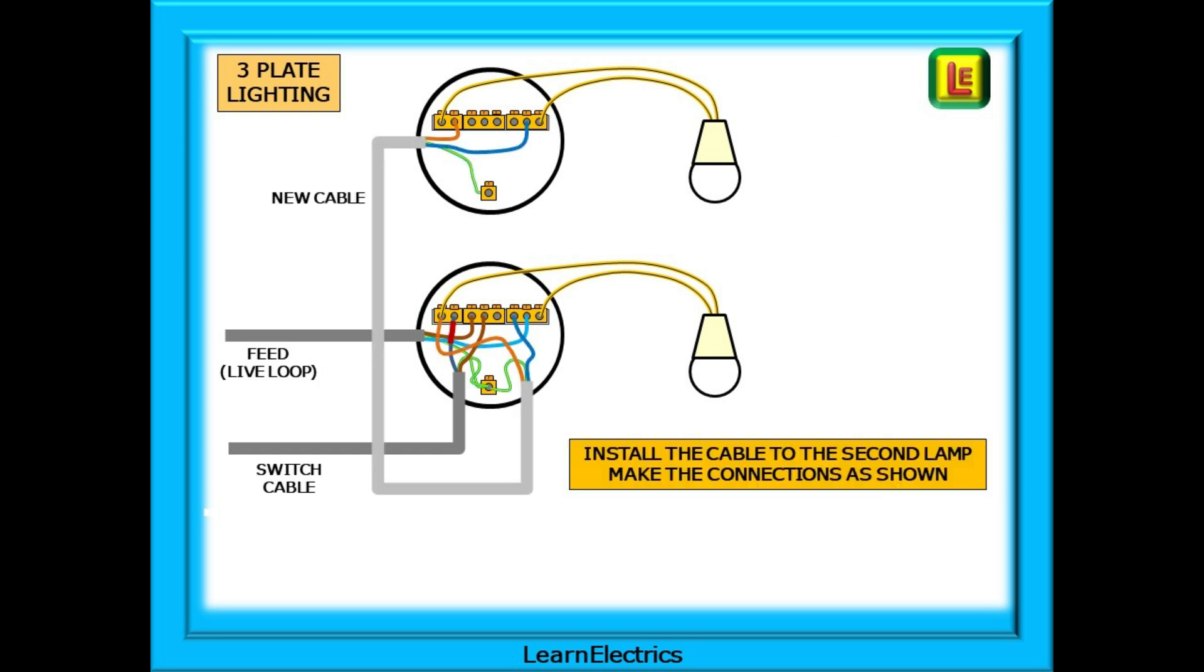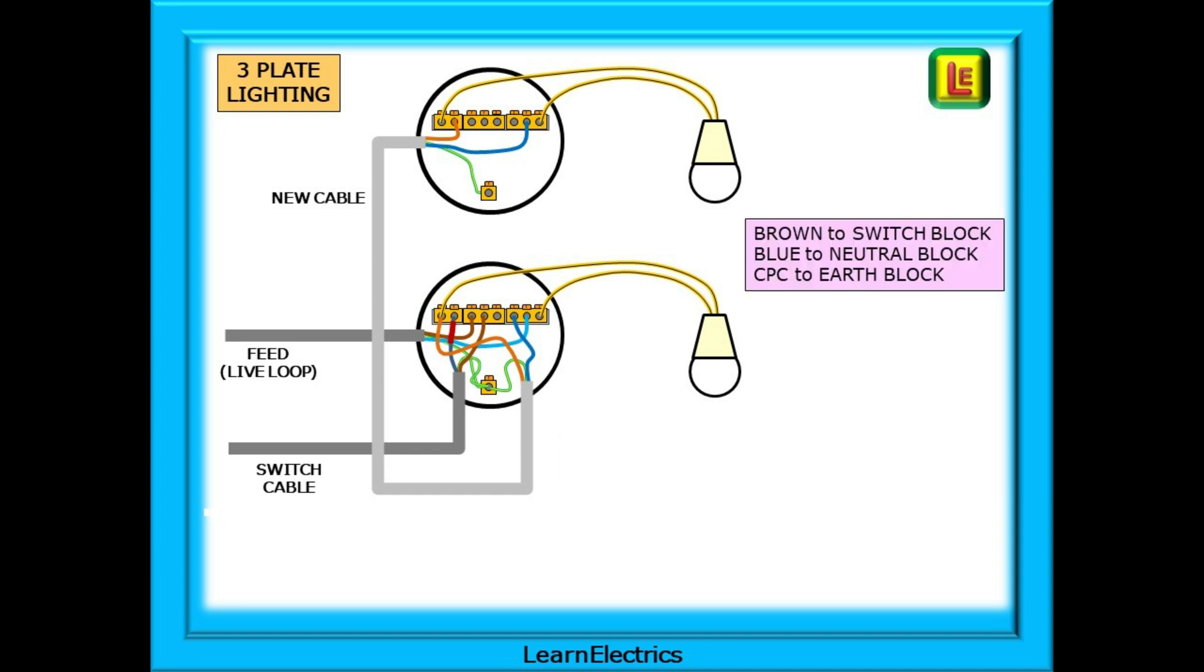Install the new cable now in the same manner as for the two-plate circuit. Note that the live loop conductors are not taken to the new second ceiling rose. The middle block of three holes is left unoccupied on the new ceiling rose. The brown will go into the two-hole switch block on both ceiling roses. Then we can connect the blue into the outside block of three holes, the neutral block, on both ceiling roses, and finally connect the CPC into the earth terminal on both to complete the installation.